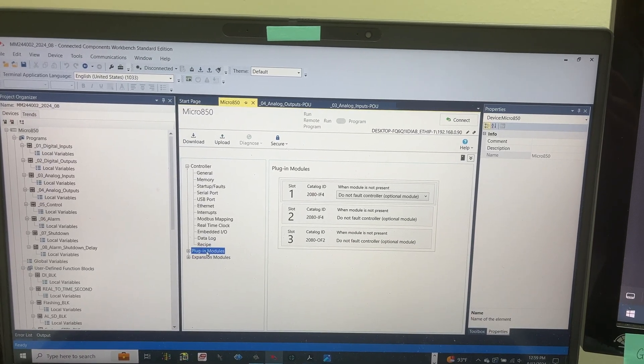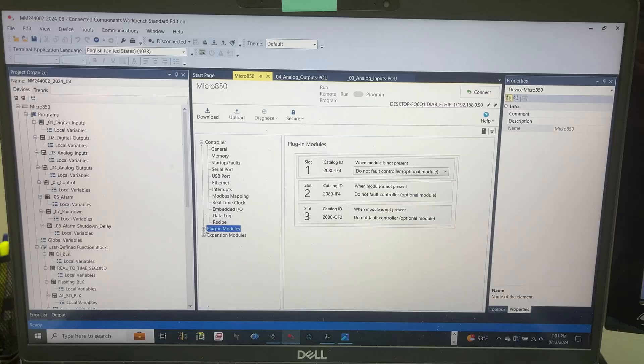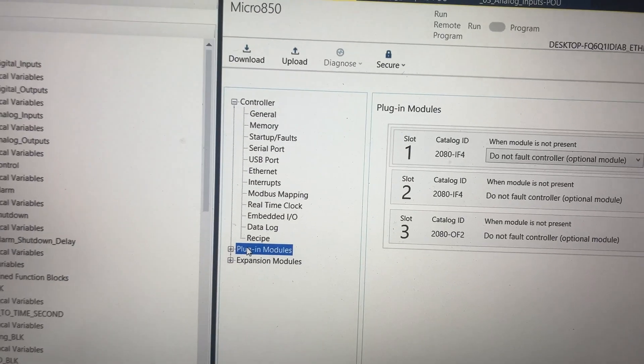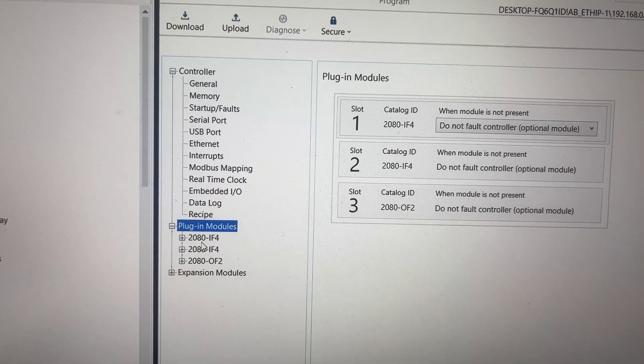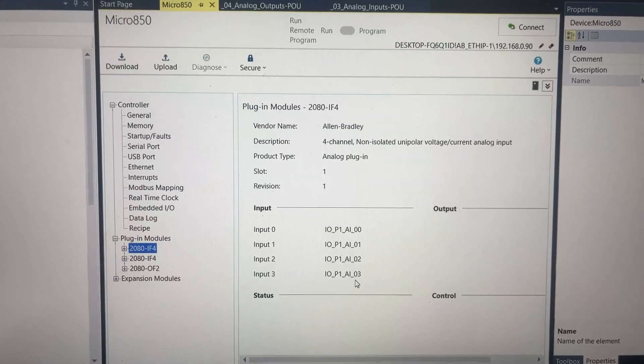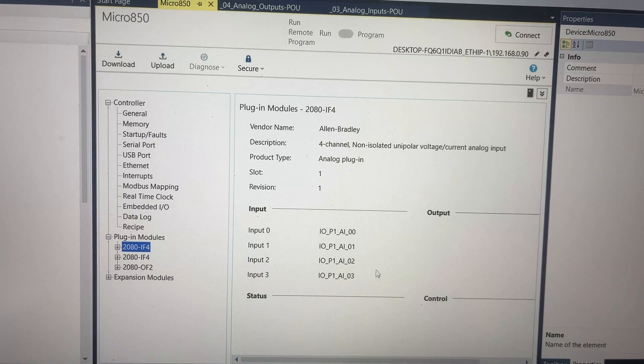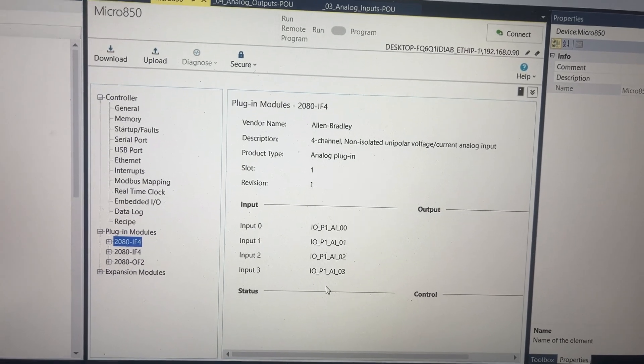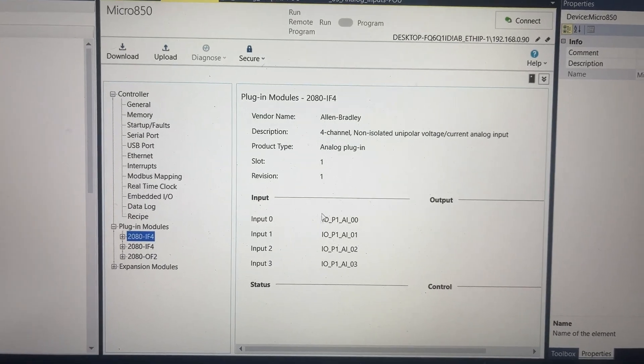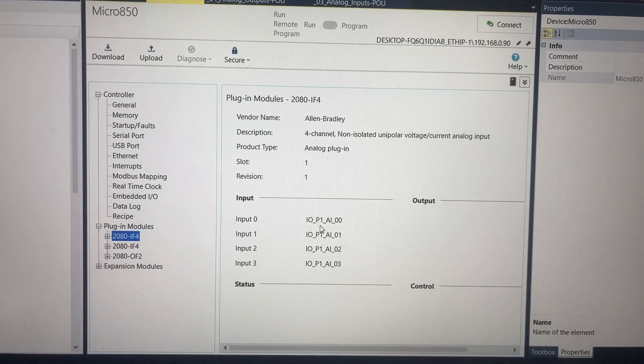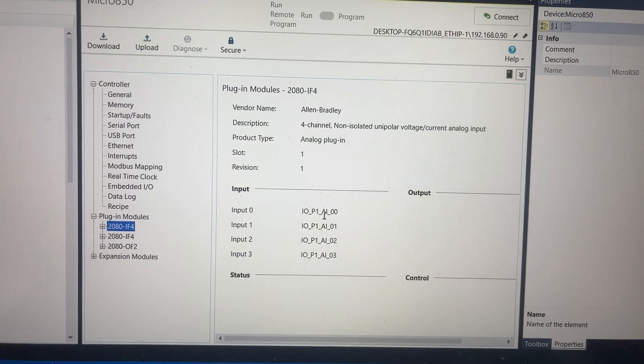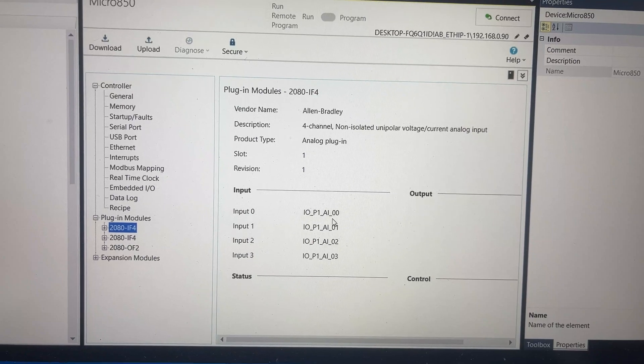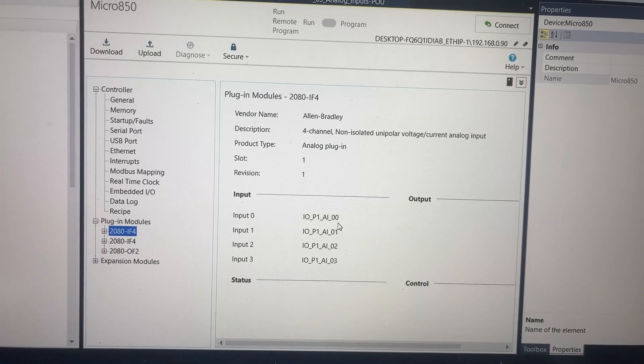In Connected Components Workbench, this is the configuration for the plugin module 2080-IF4. These are the PLC tags for the actual analog inputs on the plugin module. We have I-O for I-O modules underscore P1, P for plugin, 1 for the first plugin module, underscore AI for analog input, underscore 00 for channel number.